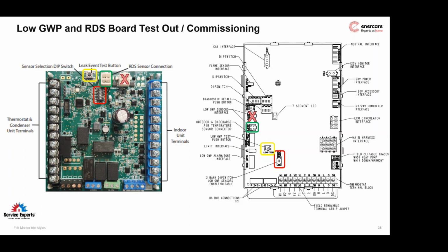Again, just a reminder, for Lennox specifically, theirs is going to turn on at about 1% concentration of the lower flammability limit. Lennox's sensor picks up, I think, around 12% of the lower flammability limit. I think Carrier's is either 15 or 17, but they're all kind of in that same neighborhood. They're all going to mitigate refrigerant down at that kind of 1 to 2% concentration level. Well below the lower flammability limit for sure.